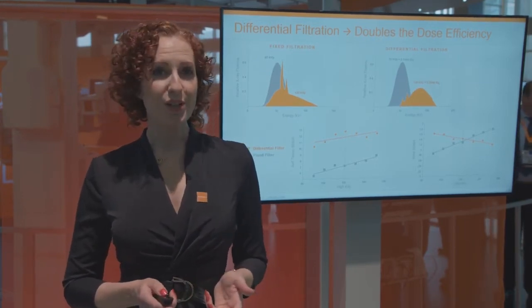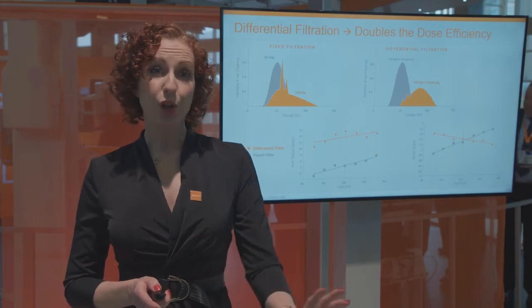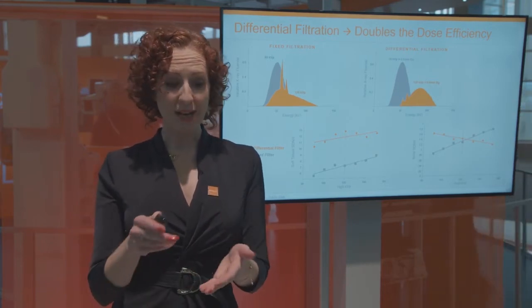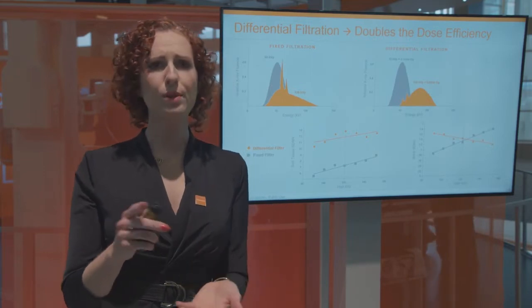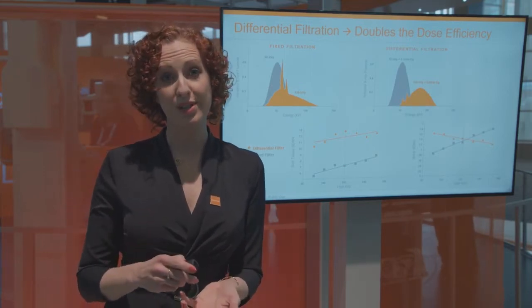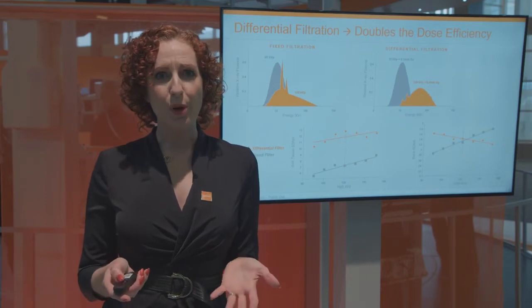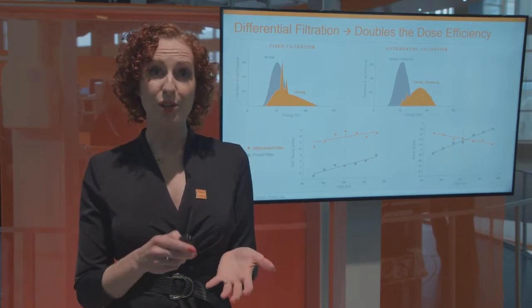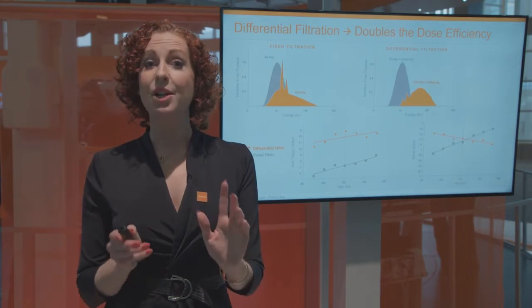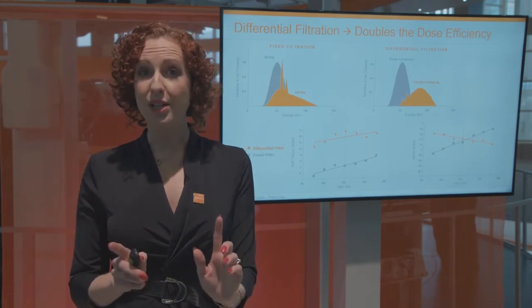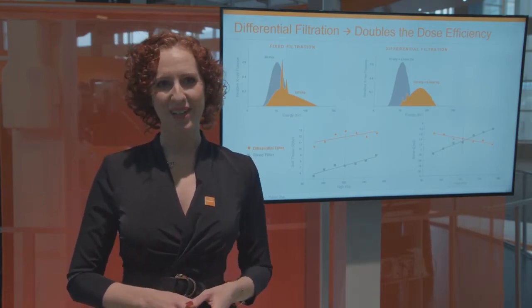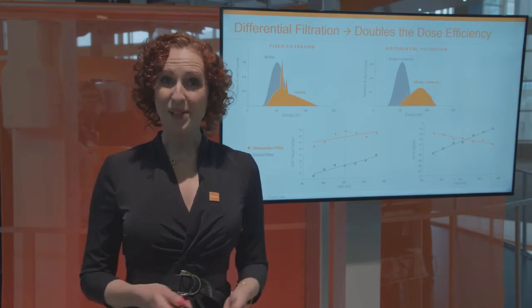CareStream dual energy technology uses an approach with two different filter materials. The filters are placed in front of the X-ray beam paths and automatically switch between the high and low-energy exposures. This differential filter approach optimises the two X-ray spectrums, and also delivers excellent image quality at an equivalent patient exposure as a standard non-dual energy chest radiograph. This is a massive breakthrough.